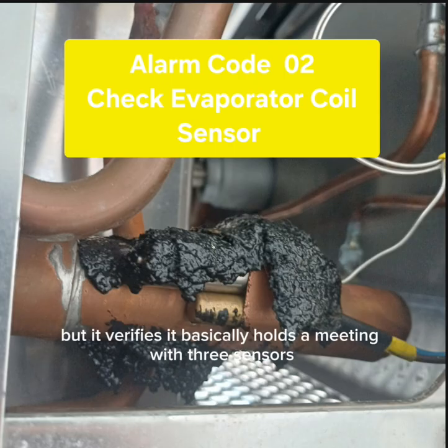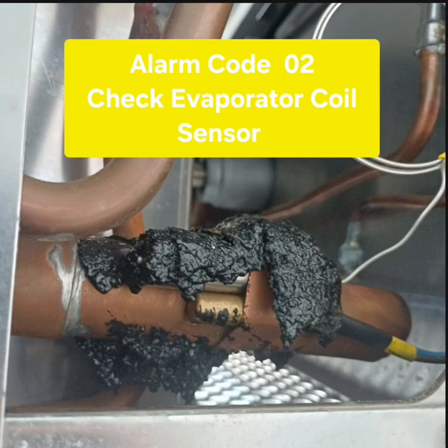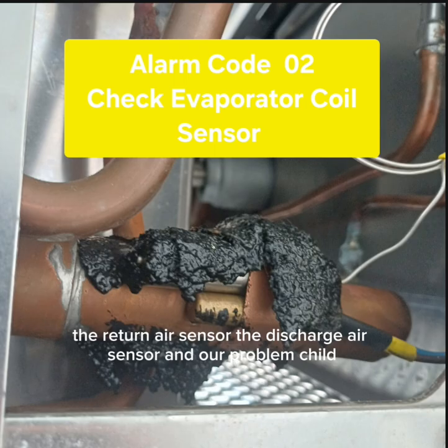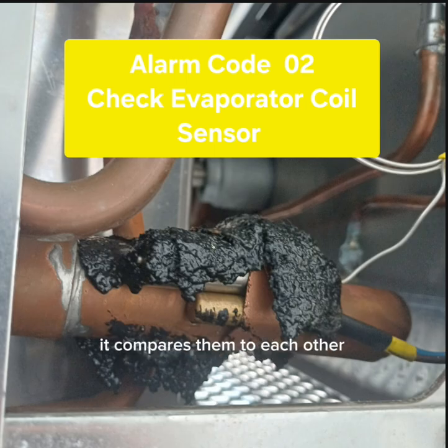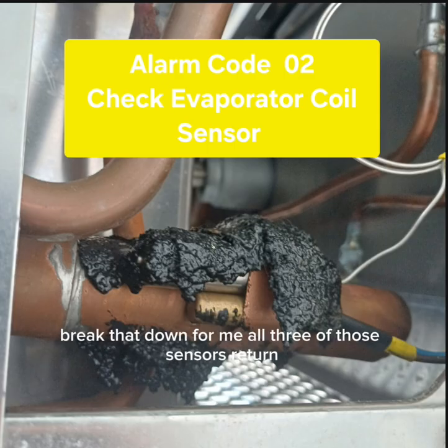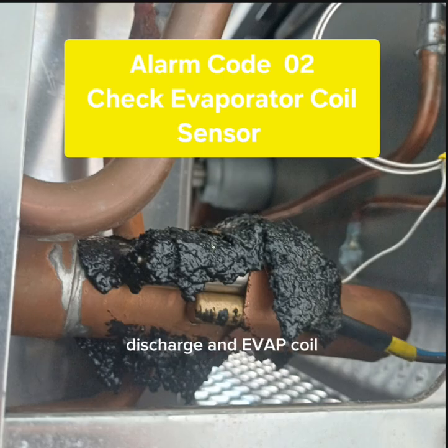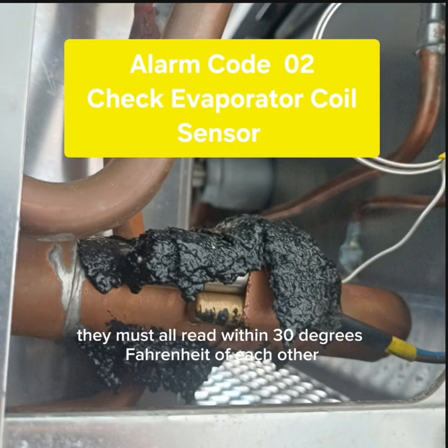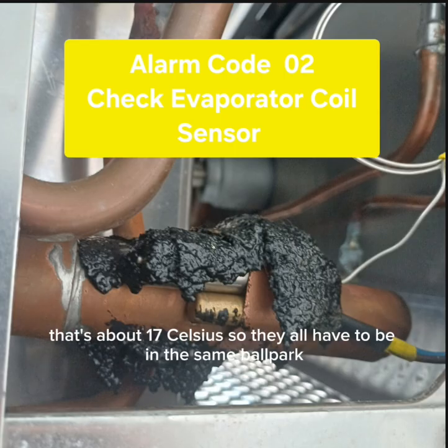It basically holds a meeting with 3 sensors: the return air sensor, the discharge air sensor, and our problem child, the evaporator coil sensor. It compares them to each other. It does, and has a very strict rule, the 30-degree rule. The 30-degree rule, break that down for me. All 3 of those sensors, return, discharge, and evap coil, must all read within 30 degrees Fahrenheit of each other. That's about 17 Celsius. So they all have to be in the same ballpark.